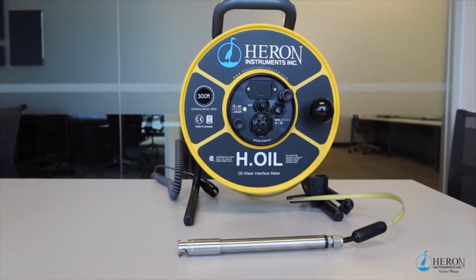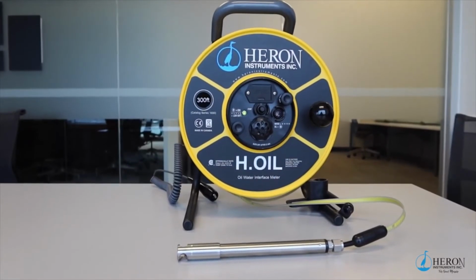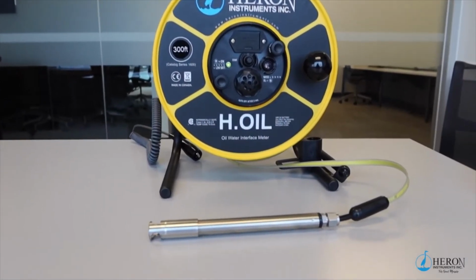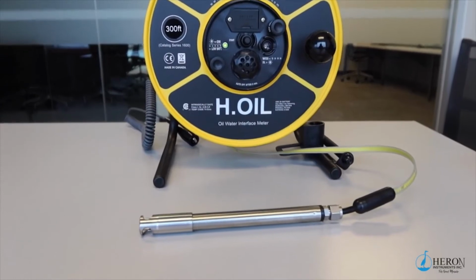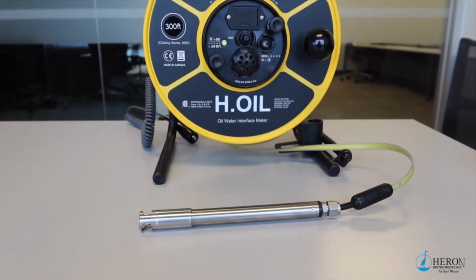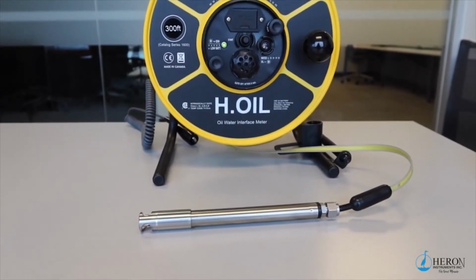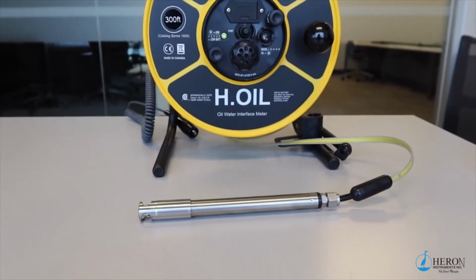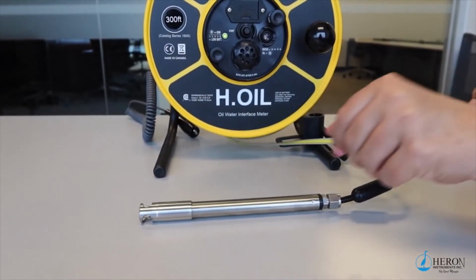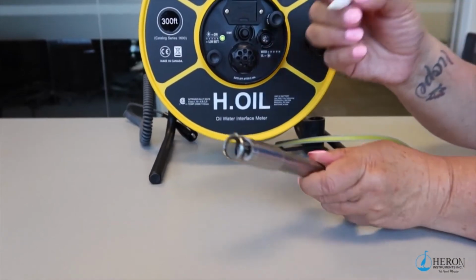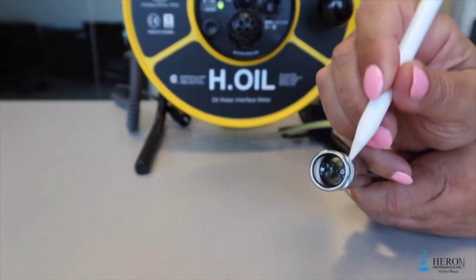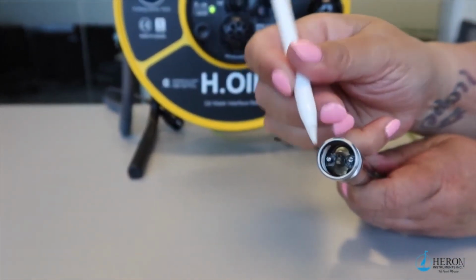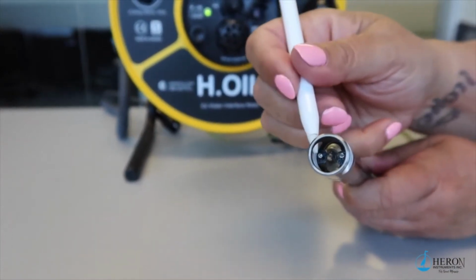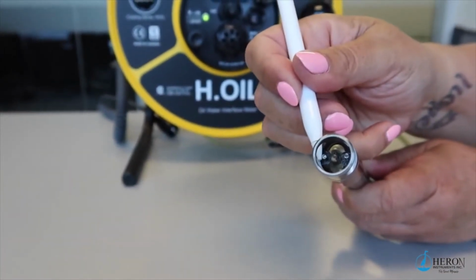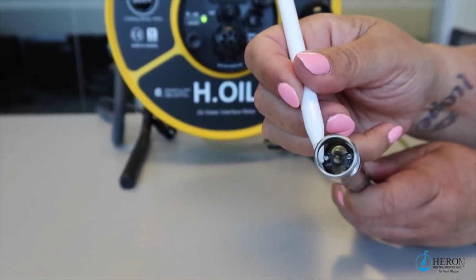The H-oil comes with a fully submersible, removable interface probe. This probe is used to detect both product and water. When you lower the probe into the water or product, the unit will start to sound immediately. Please note that both the pins in the lens need to be submerged in the water or product to create the contact. The shortest pin in the lens is the 0 point to the first foot or meter mark.